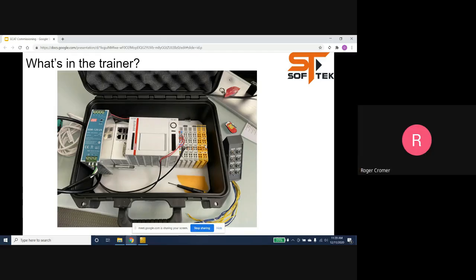A lot of our customers will generally specify how they want them done, because it helps with their programming on their side. So with applied materials panels, if there are safety slices in it, they'll generally specify that we want the first one set to 1, then 2, 3, 4, 5, 6, like that. Some people will want them to be specific numbers that match the actual number of the slice in the code, so if it's terminal 36, they might want to start at terminal 36, but it's always worth consulting with the customer to find out. It's also worth noting it, so you can tell the customer, hey, we've set these and these are the values, because if one of the slices dies in the future, it's easier for the customer to know they need to replace it with a new one set to the same dip switch settings, scan it in, and run the system immediately, instead of having to figure out how a new slice is affecting the system.